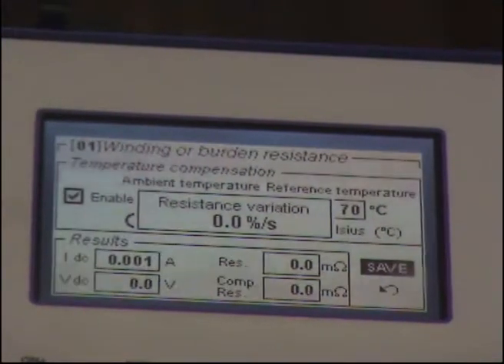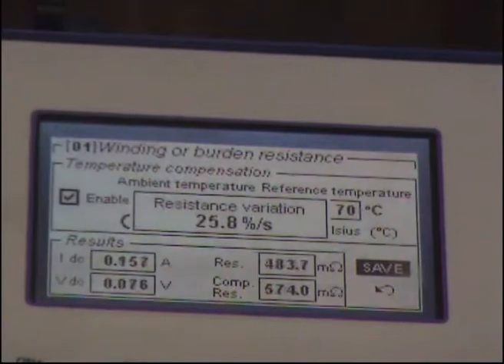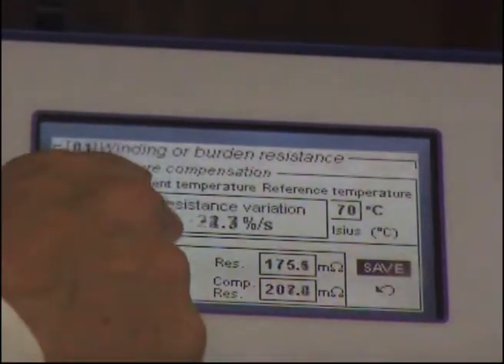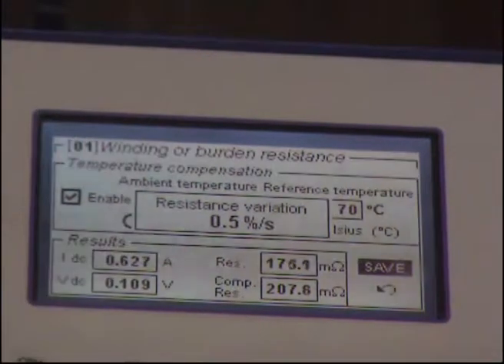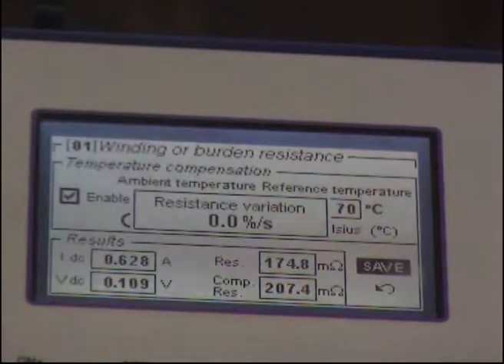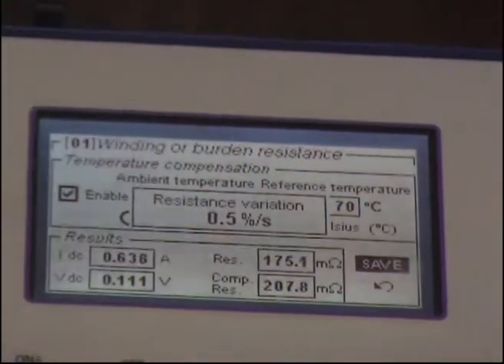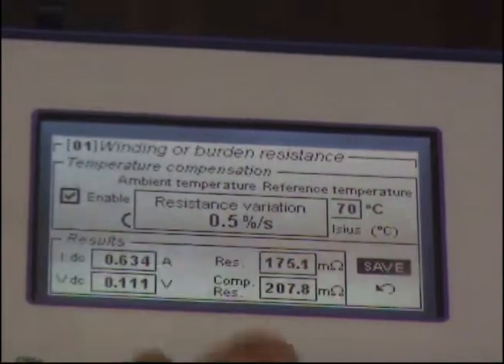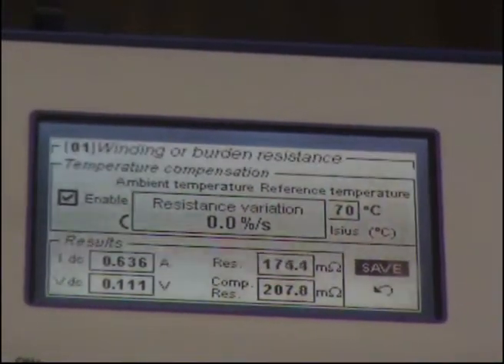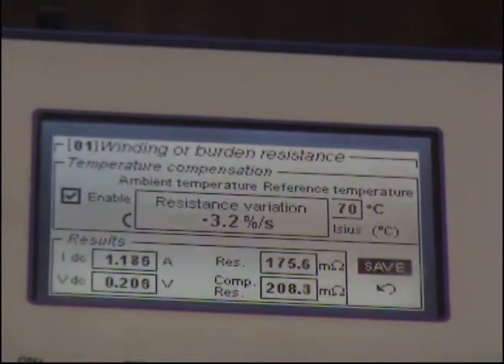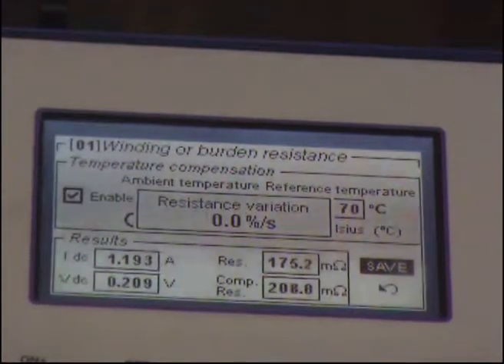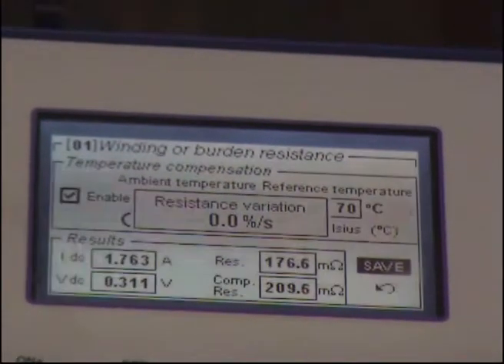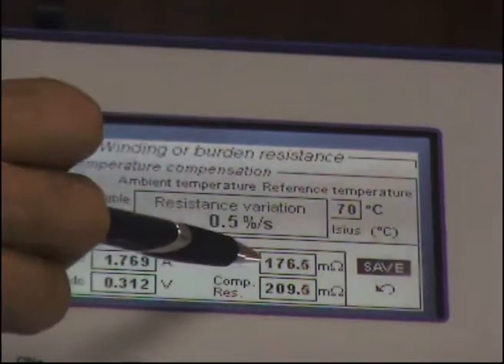Now, I increase the current slowly. You see, as I do, there is this message here telling me that the resistance is changing. So this means that due to the inductance, the measurement that I am doing at the very moment when I increase the current is wrong. But at some moment you can see that even if I keep on increasing my test current, the resistance here doesn't change anymore. And you see that the resistance at my temperature now is 176. The resistance at 70 degrees would be 209.